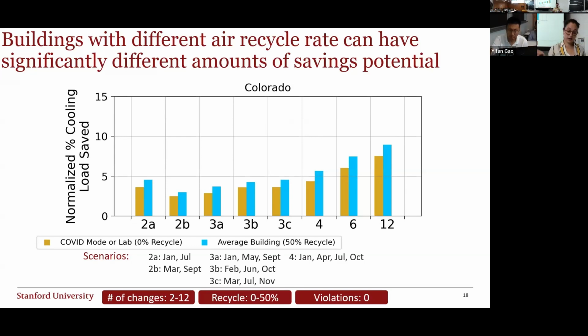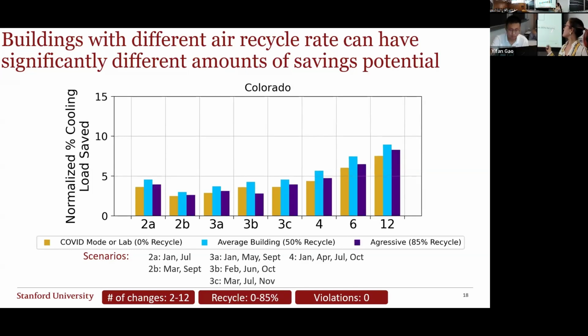Here, the COVID mode or lab mode basically means 0% recycle—meaning all of the air going through the system is outside air, and none of the indoor air is put back into the system. What you can see is that with 0% recycle, the savings are lower for each scenario, which makes sense since we're at the mercy of the outside air conditions.